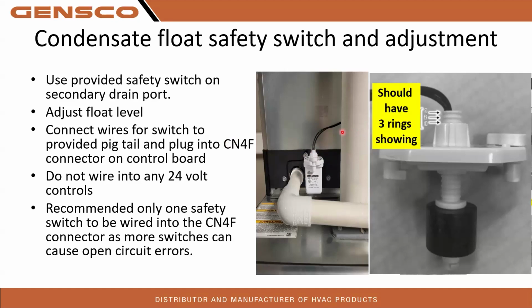If it does not have that CN4F connector plugged in, or if it's got too many safety switches, or if it's got any 24-volt control wiring going to it, you do not want 24 volts running through that circuit. But you will get a float switch error or limit switch error, depending on what you're using, whatever it's reporting as. Recommended only one safety switch on that circuit.